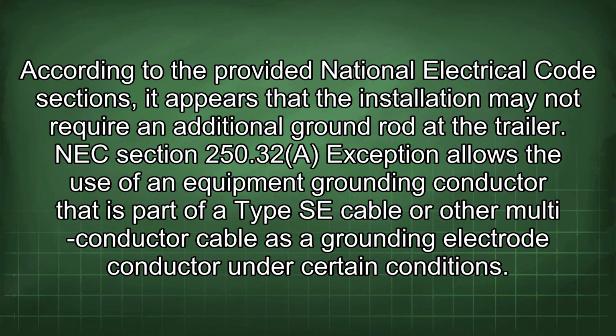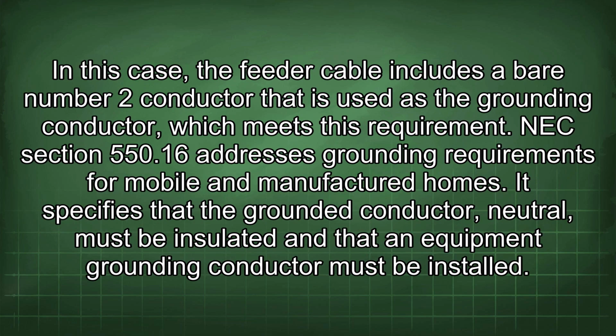According to the provided National Electrical Code sections, it appears that the installation may not require an additional ground rod at the trailer. The NEC Section 250.32 exception allows the use of an equipment grounding conductor that is part of a Type SE cable or other multi-conductor cable as a grounding electrode conductor under certain conditions.